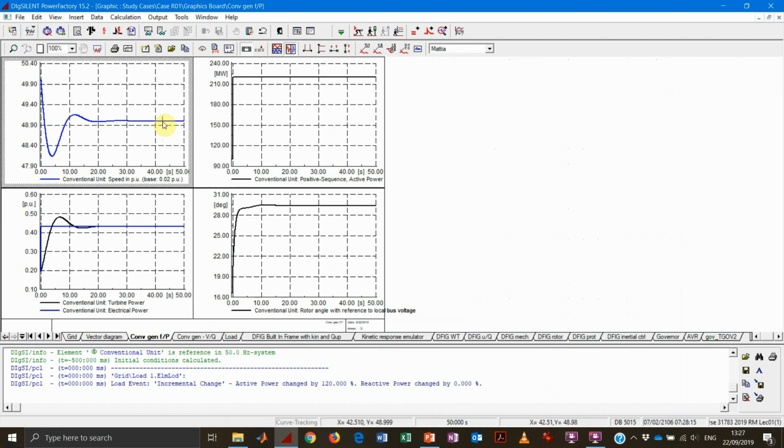In this case, we of course experience a worse frequency in our system, and the new value is basically 49.0 Hz, which is what we'd expect, because we are deploying half of the reserve, because the droop got twice as much. And so the intensity of the response got half of the original one. And so the steady state frequency, given that we have the same load step, will be lower. In this case, 1 Hz lower than the nominal frequency.